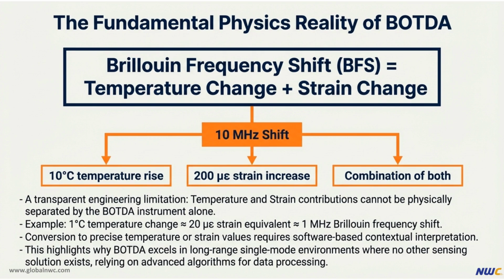The key principle behind BOTDA technology is that the Brillouin frequency shift reflects the combined effect of temperature and mechanical strain. However, there is an important engineering limitation. When a change of about 10 MHz is detected, the system itself cannot directly determine whether the shift was caused by temperature variation or tensile strain. Therefore, achieving precise interpretation requires more than measurement alone. Contextual analysis through software and advanced algorithms plays a crucial role in accurately distinguishing and interpreting these changes.